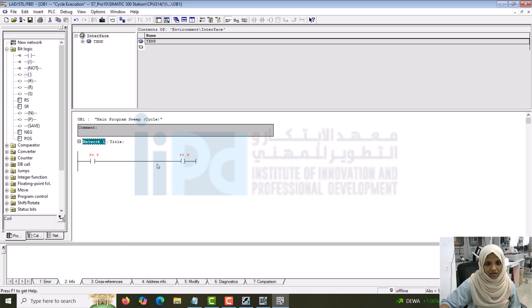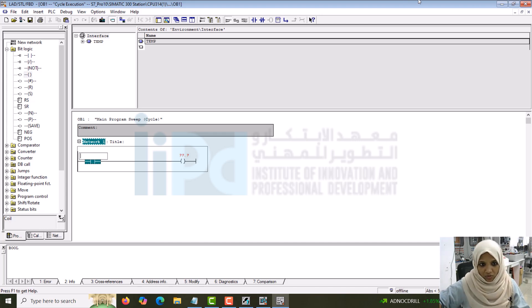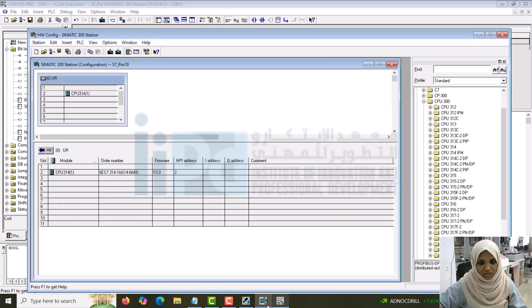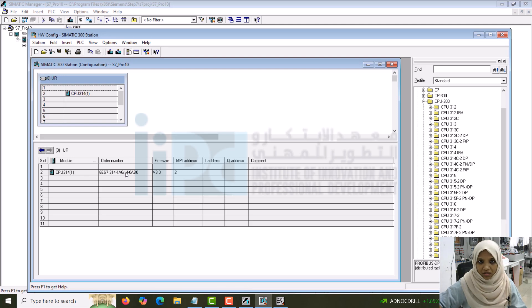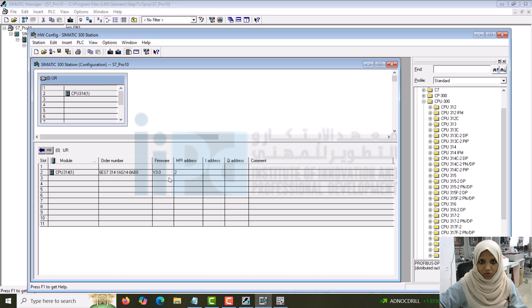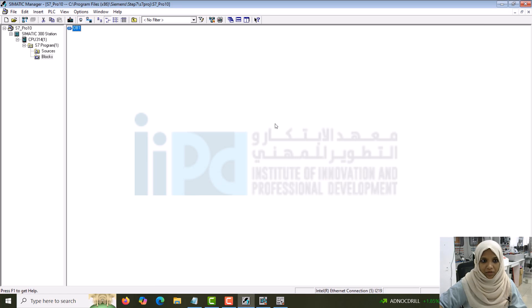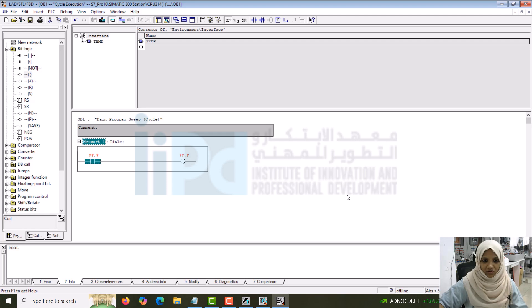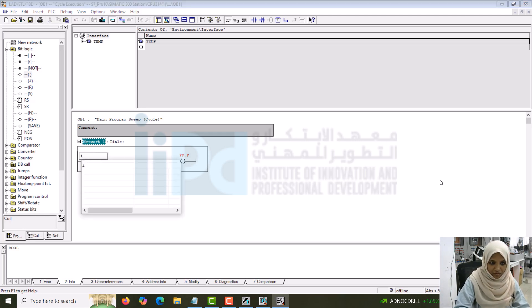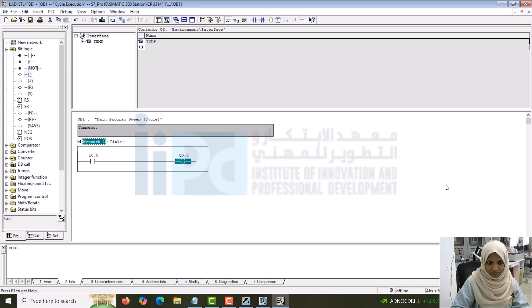Our next important thing is we have to assign the address. Let me give the address. It starts from I0.0. When you do with hardware, you have to make sure what is the display for your input, output, etc. What address is given for your IO modules, what address is assigned for your IOs will be displayed here. According to that, you can give the addressing inside the main program. For now, you can directly start with I0.0, Q0.0, etc. Input will be I. This is the first input. Output will be Q0.0.